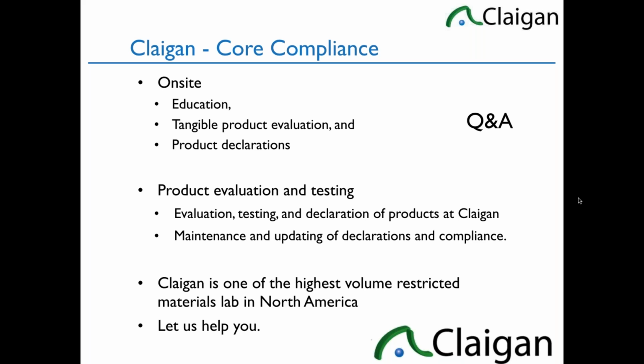How about EU MDR and the list of 1,000 substances? How do you manage it? Again, we approach risk. Everything has to be managed through risk. MDR, that one, I would say, especially the CMR side, we are the world's experts on how to do it in practice. So what you do is you take the category 1 carcinogen, mutagen, reproductive toxin. For those who aren't doing medical device regulation, a vast oversimplification: materials that are invasive or touch fluid that goes into the human body, or gas that goes into the human body. If it's got a category 1 known carcinogen, mutagen, or reproductive toxin above 1,000 ppm, you have to do a variety of things, including justifying it as part of the product registration, but also labeling and other communication requirements.